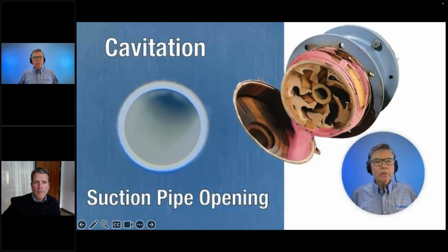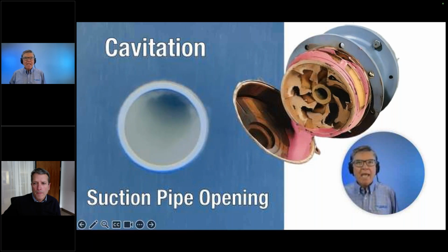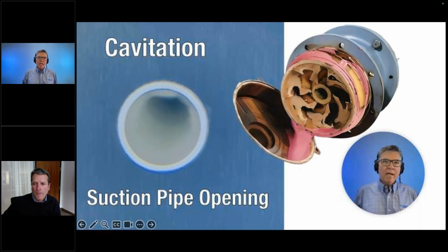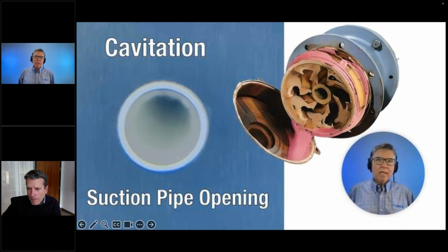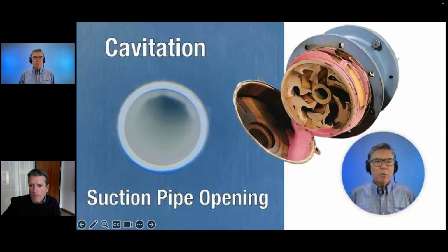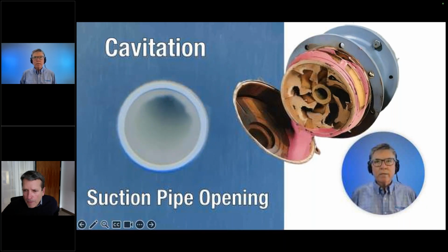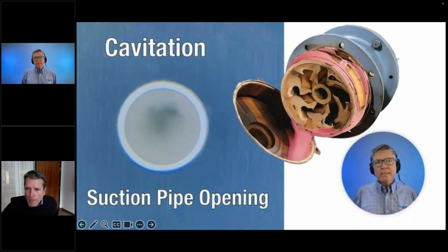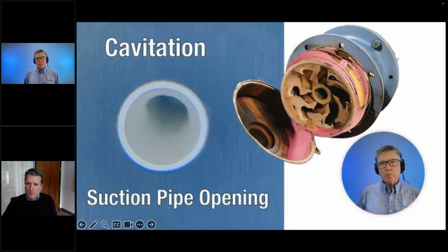So here is a video of cavitation. So what cavitation is, it's the pressure gets so low inside the pump or in and around the pump impeller, which you can see one that's been just destroyed by cavitation up above. But literally, the water pressure gets so low, it vaporizes water.